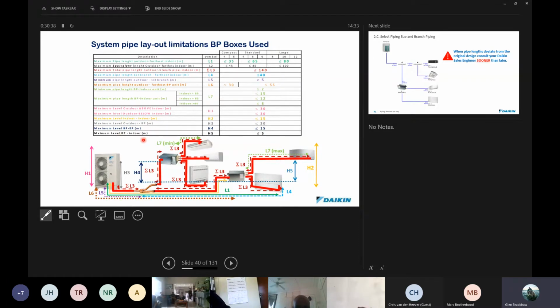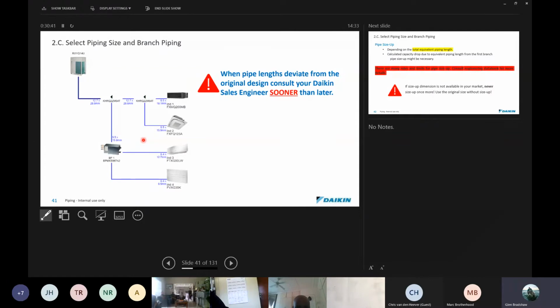Okay. All right, so this will be a typical schematic that somebody would build a VRV or install a VRV system off of. Okay, and what's important here, okay, when the pipe lengths deviate from the original design, consult your Daikin sales engineer sooner than later. Right, so in this particular schematic, there are no pipe lengths, but this is something that a person will have on site. They must have on site while they're installing, and they should be updating this on a frequent basis. So basically at the end of a day, they should be looking at how much piping they laid, and they can actually go and say, right, well, today we laid piping here, here, and down to here. We should now be able to measure that and start adding it up. Okay, and then they should start seeing whether they're hitting a problem on there.